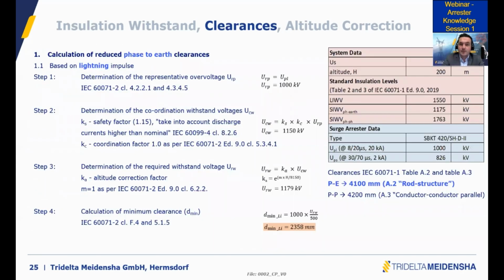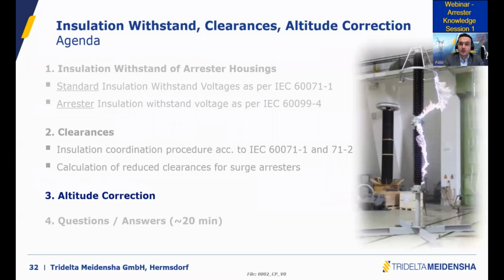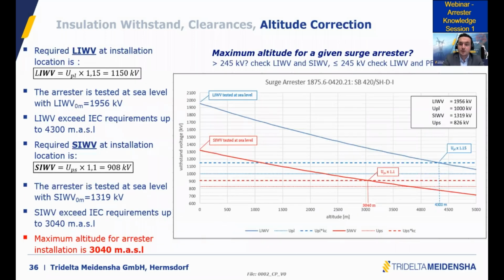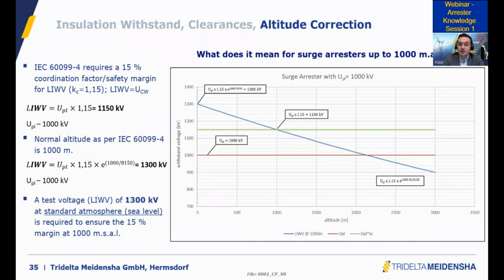Let me jump to the right slide. Typically here, yes. When we look at this slide, the blue curve that you see is actually using an exponential of (1,000 minus the altitude), because we are specifically interested to know the required lightning impulse withstand voltage for a specific altitude. But the graphic could be confusing. The same concept applies to the bushing.